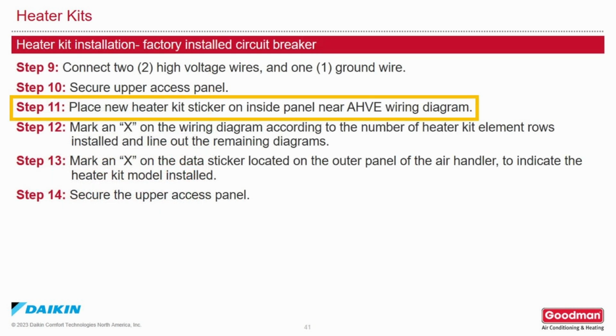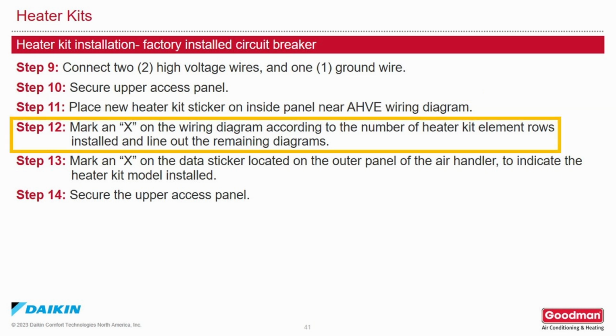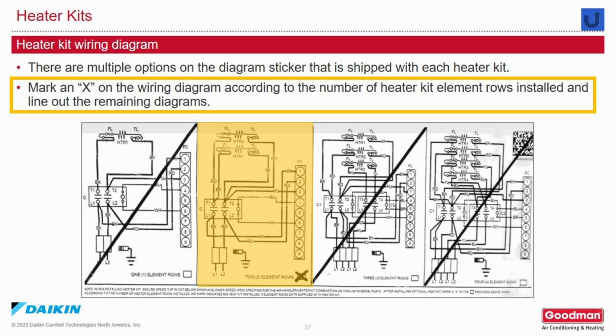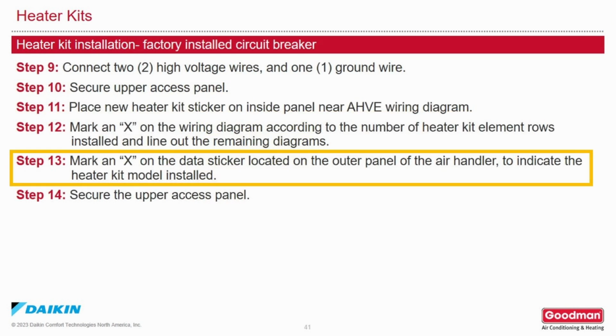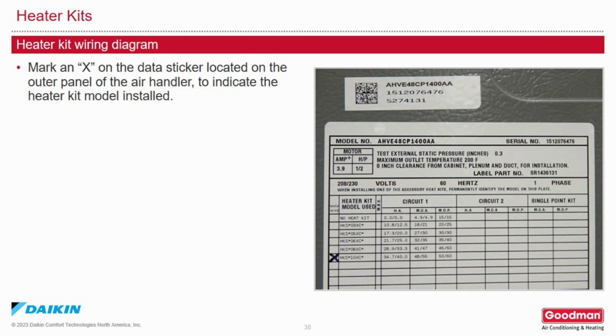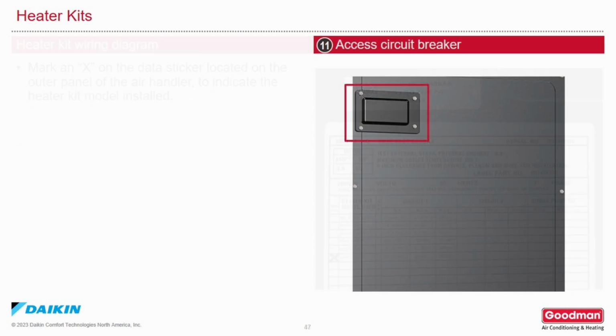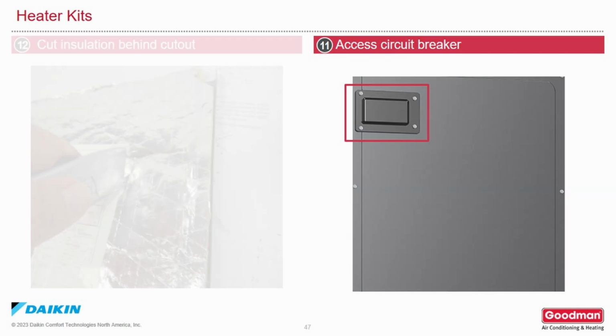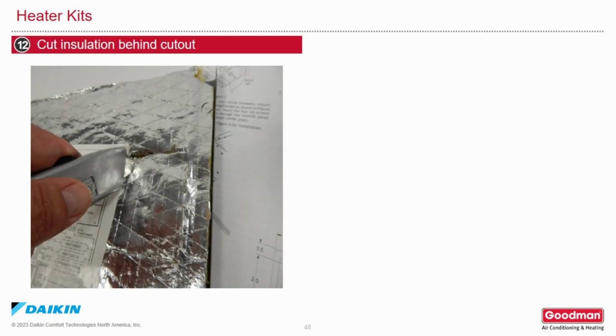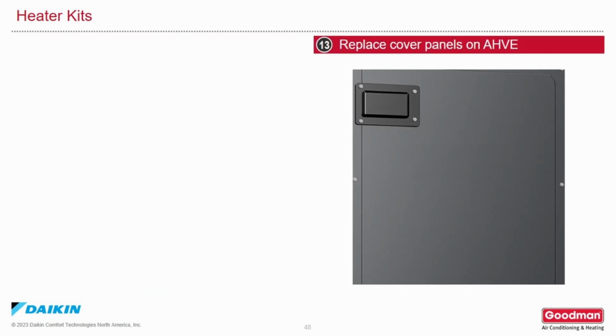Place the heater kit sticker on the inside panel near the AHVE wiring diagram. Mark an X on the wiring diagram according to the number of the heater kit element rows installed and cross out the remaining diagrams. Mark an X on the data sticker on the outer panel of the air handler to indicate the heater kit model that was installed. Access the circuit breaker. Cut the insulation behind the cutout and replace the cover panels on the AHVE.